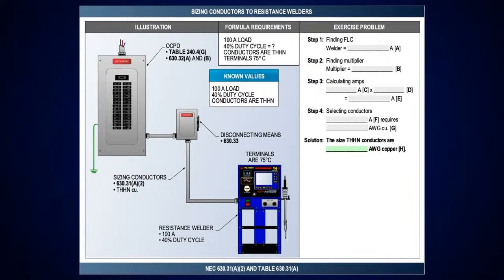All right. And then here we got a 100 amp load, 40% duty cycle. So you should know automatically in step 1, it's 100 amps. Step 2, I'm looking at table 630.31A, picking up my 40% duty cycle. Get your multiplier, multiply those two together, and whatever your amperage is, you size your conductor based off of that.